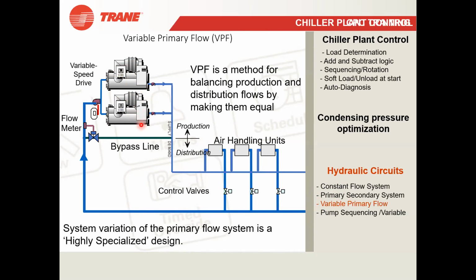So in this case, the primary pump takes care of the complete system flow requirement without compromising the minimum flow requirement of the chiller. I have told you and made you understand that the minimum flow requirement of the chiller has to be maintained, otherwise evaporator freezing will happen. These can be controlled by the CPC, which is very difficult to control otherwise. Variable primary flow is very difficult to control manually. So the CPC is a great help for controlling this kind of complex system.